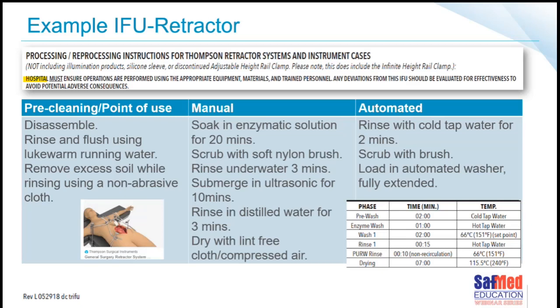Number one. Number two, if you're doing a manual process, so firstly you need to do the pre-cleaning, then you do the manual process. Say you don't have a washer. Your next job is to soak this device in an enzymatic solution, obviously mixed correctly, for 20 minutes. I've never seen anybody soak any device for 20 minutes when cleaning it. Scrub with a soft nylon brush, then rinse under water for 3 minutes. Then submerge in the ultrasonic cleaner for 10 minutes. It also specified the hertz, so how strong the ultrasonic cleaning should be. Then rinse in distilled water for 3 minutes. Then dry with a lint-free cloth and or compressed air.